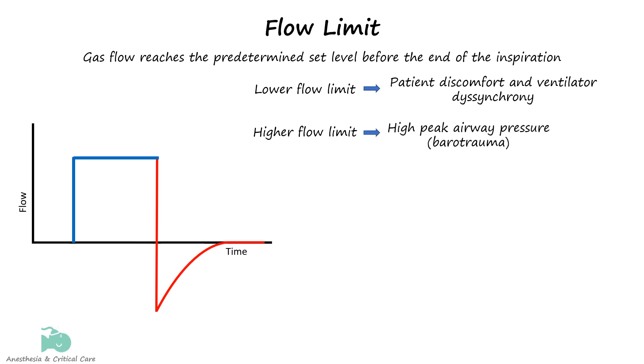For reference, the typical peak inspiratory flow rate of a calmly breathing person is 30 liters per minute, and it can increase to over 200 liters per minute in an athletic individual performing heavy exercise. Modern ventilators have a theoretical maximum flow limit of about 200 liters per minute. Typical inspiratory flow limit is set at about 60 to 120 liters per minute.